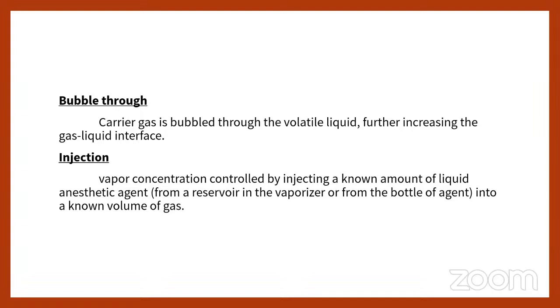So, for example, for 1 liter of fresh gas, we will be giving 100 ml of anesthetic agent. So the total will be 1.1 liters of fresh gas mixture delivered to the patient. If we multiply the fresh gas flow, if we take 5 liters of fresh gas, 500 ml of anesthetic liquid will be injected into the fresh gas, and the mixture will be delivered to the patient. This is the injection system.